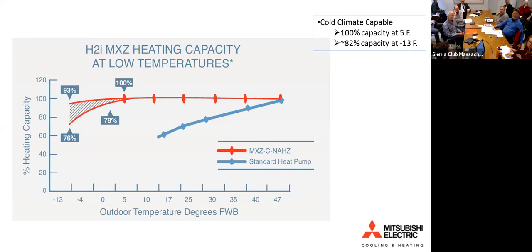So it's a design component. You design it to be able to carry your design temperature and what you need for capacity at that low temperature. Our design temperature in Massachusetts, in Boston, I think is 7 degrees. So at 5, we're getting 100% capacity, which is a game changer, complete game changer. And all the manufacturers have this. It's not just Mitsubishi, which is great for the industry. It's allowing us to take this technology and put it all over the United States, including Canada.